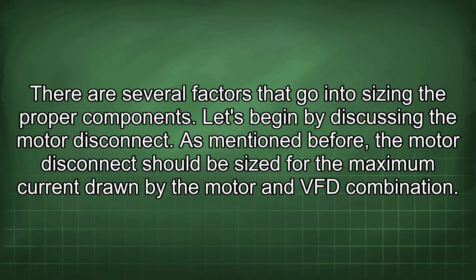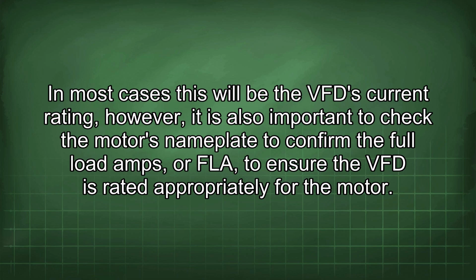There are several factors that go into sizing the proper components. Let's begin by discussing the motor disconnect. As mentioned before, the motor disconnect should be sized for the maximum current drawn by the motor and VFD combination. In most cases, this will be the VFD current rating. However, it is also important to check the motor's nameplate to confirm the full load amps, or FLA, to ensure the VFD is rated appropriately for the motor.